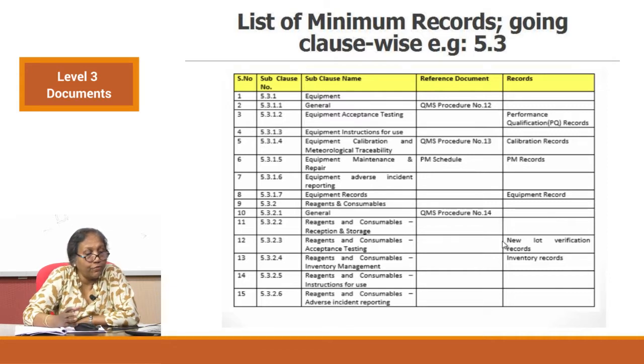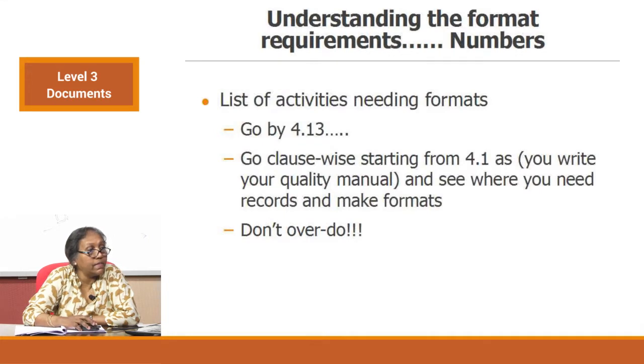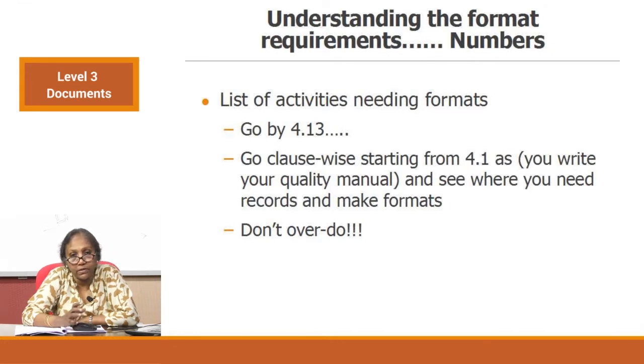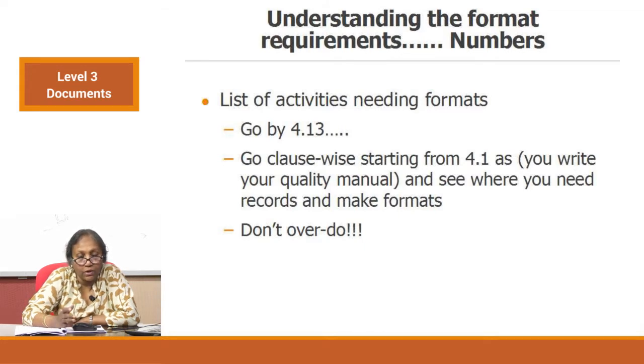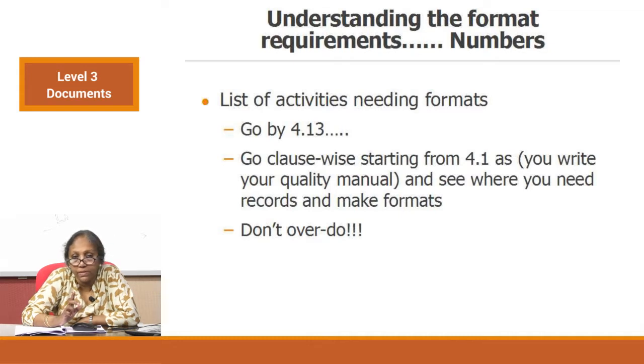Regarding the number of formats: go by 4.13 or go clause-wise starting from 4.1, and as you write your quality manual see where you need records and make formats. But do not overdo it — do not think that more formats means a better quality management system. Do not make unnecessary formats because eventually technicians will be required to fill them up and unnecessary activity will burden them. However, evidence required for audits or review meetings must be captured, and that is where 4.13 is of great value because those are documents that will be audited.